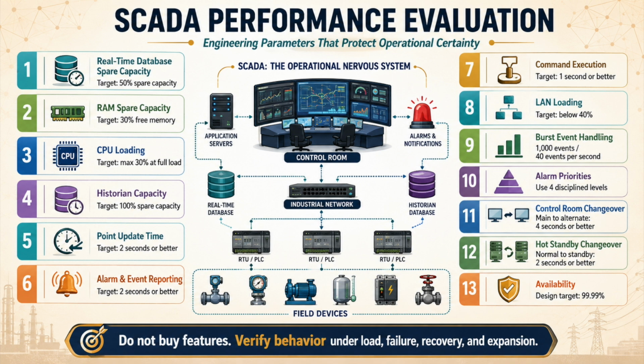Network health is not only bandwidth, it includes latency, jitter, packet loss, broadcast traffic, switch loading, firewall delay, redundancy path behavior, storm control, and protocol efficiency. SCADA LAN loading should remain below 40% under the defined full performance scenario, because the network needs margin for alarm bursts, historian transfer, redundancy synchronization, client access, engineering activity, cybersecurity monitoring, backups, and abnormal communication recovery. A network running heavily during normal operation is already compromised before the abnormal situation begins.